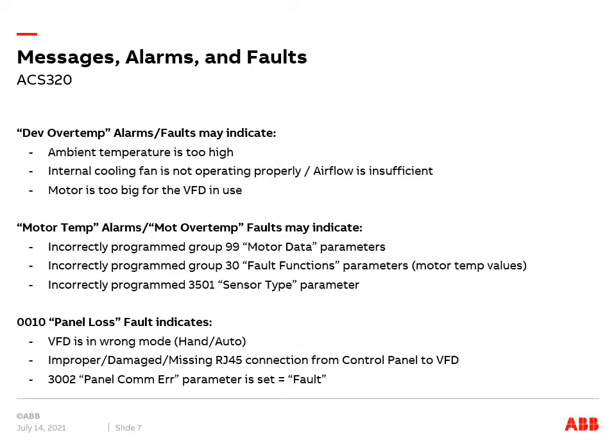Device over temp faults occur when temperature is too high and/or cooling is not sufficient in and through the VFD. They can also be triggered if the motor being run is too large for the VFD.